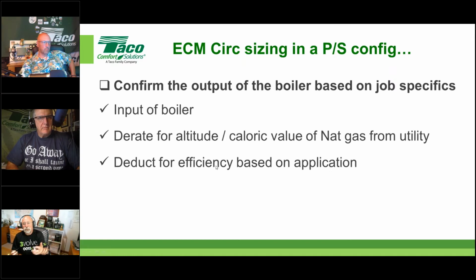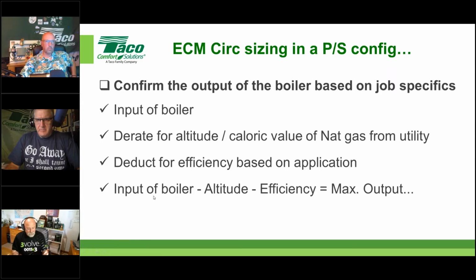Then you have to reduce the amount that the boiler can give you based on the efficiency, and that's always based on the application. Okay, if I've got a really low return temperature, let's say 100 or less coming back to this thing anytime it fires, then you're going to have really high efficiencies. But on occasion, if you're doing domestic hot water or high temperature where the return temperature is elevated to the point where you're not condensing, then you have to take that efficiency down in your circulator sizing. Okay, so it's this in a nutshell.